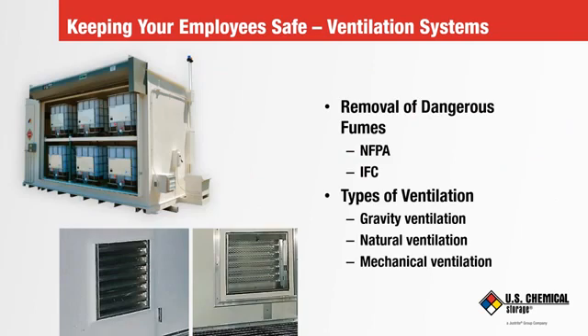There are three types of ventilation systems. There's gravity ventilation. A single opening in the lower wall of the building is fitted with a rain louver and a bird screen. Now, if it's a fire-rated building, they add a fusible link drop-down shutter. This acts as a vent. The top of the rising fumes will be pulled out of the opening by gravity like a hole in a coffee cup, allowing the fume to drift down on the ground where it eventually dissipates into the atmosphere.